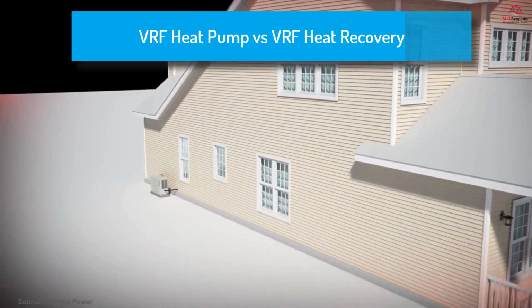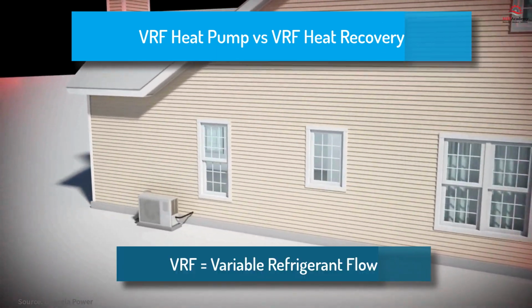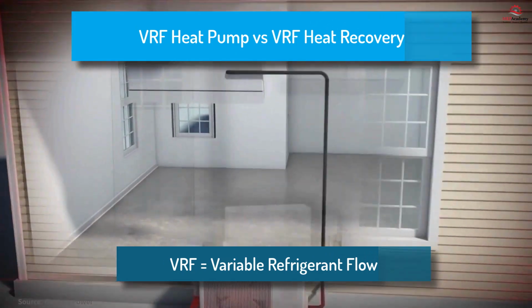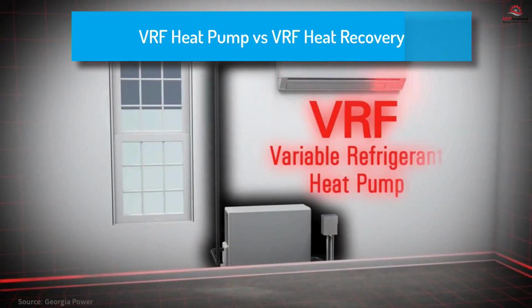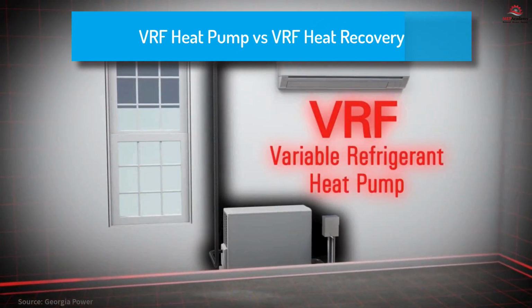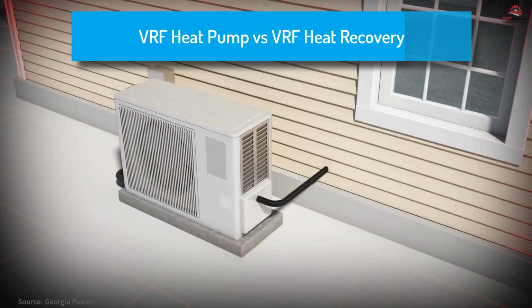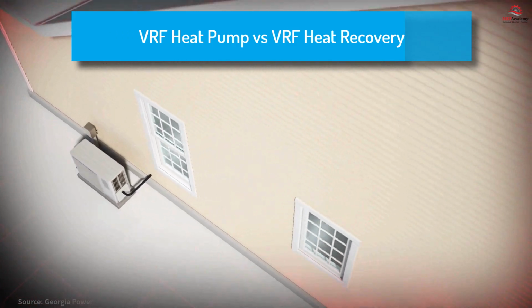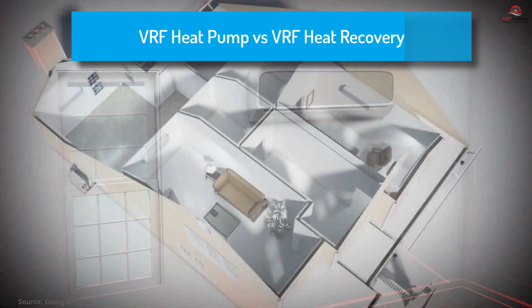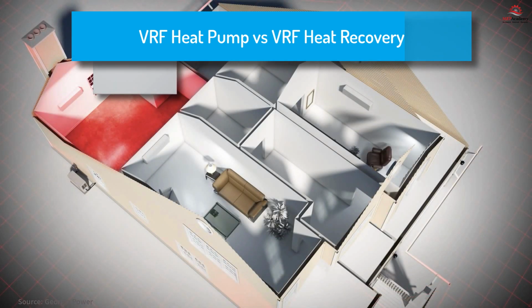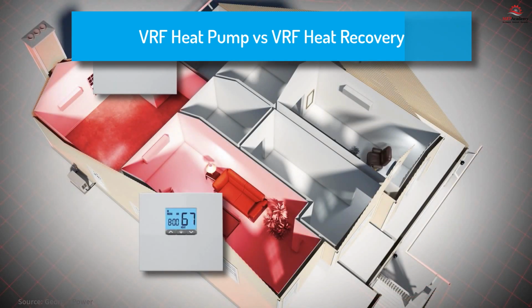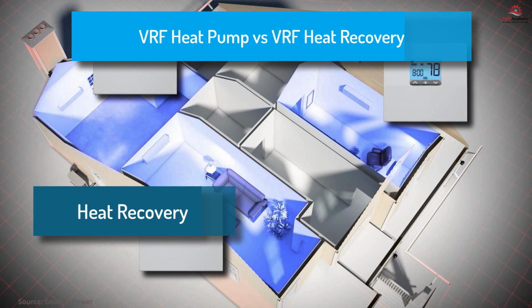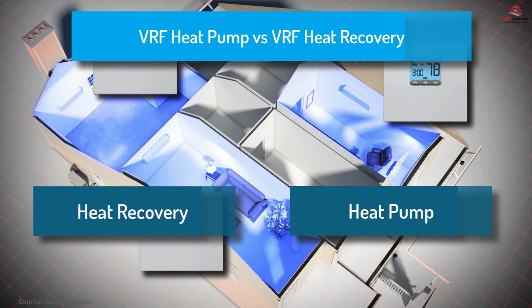VRF stands for Variable Refrigerant Flow, a method of varying the volume of refrigerant circulated in the system in relation to demand. As demand drops, so does the volume of refrigerant circulated by the compressors. The compressor can slow down and pump less refrigerant to meet the current demand of the system. We'll explain the differences between a VRF heat recovery system and a VRF heat pump.